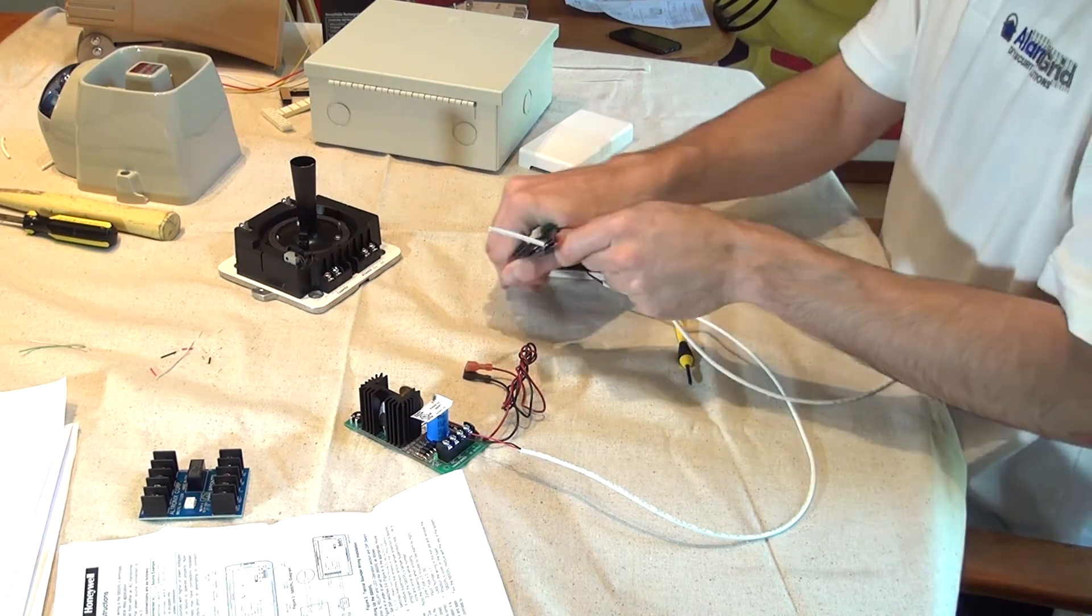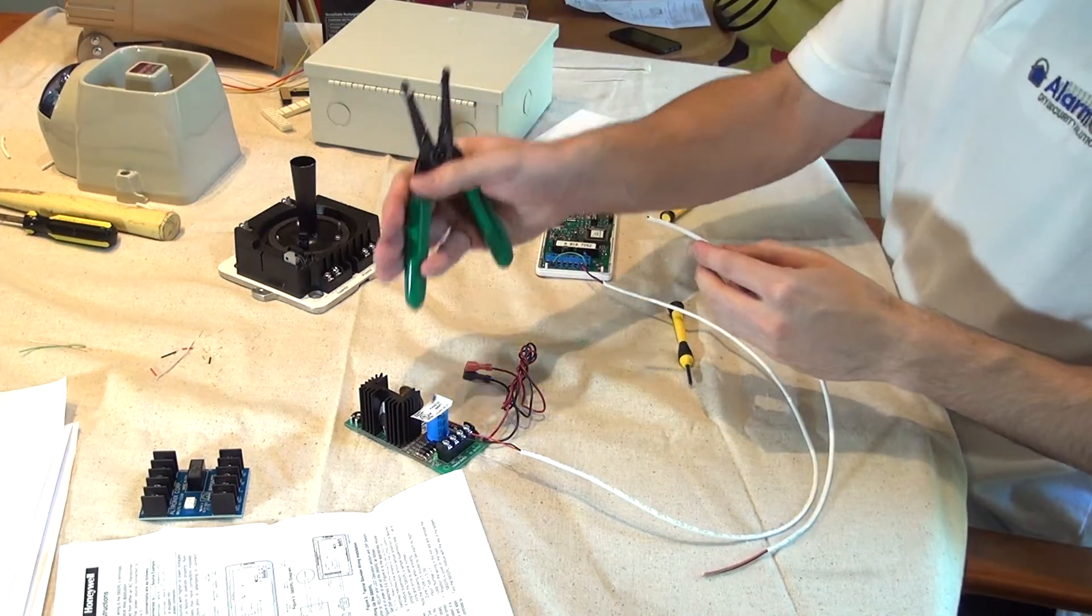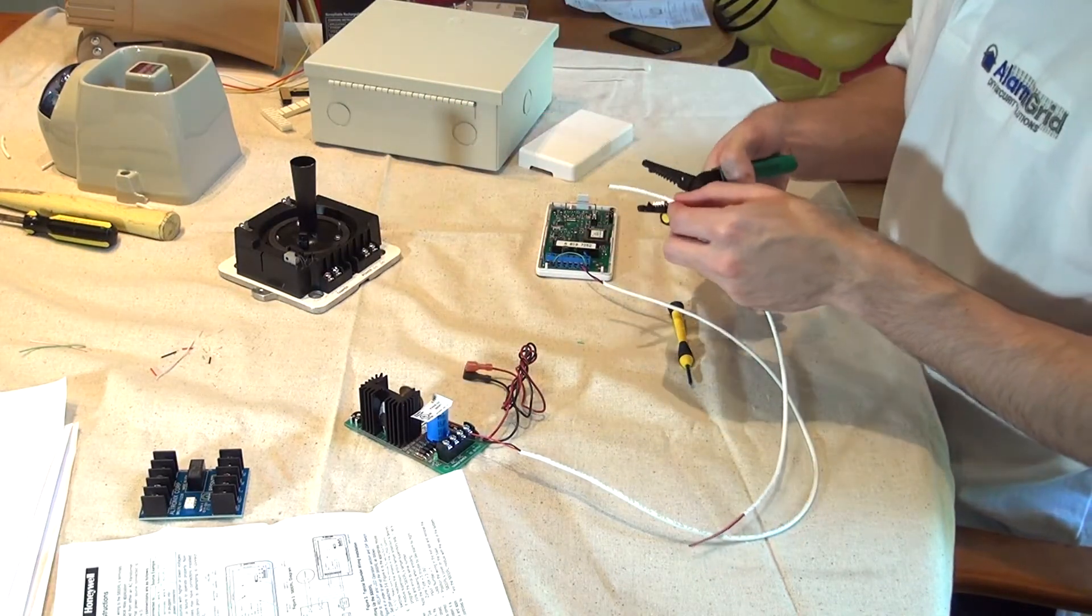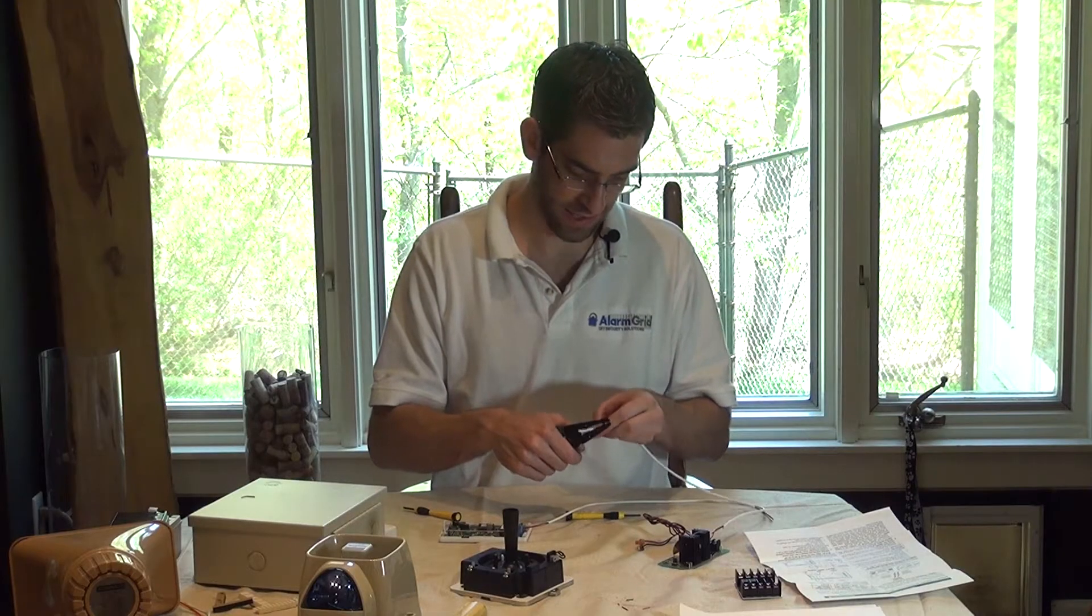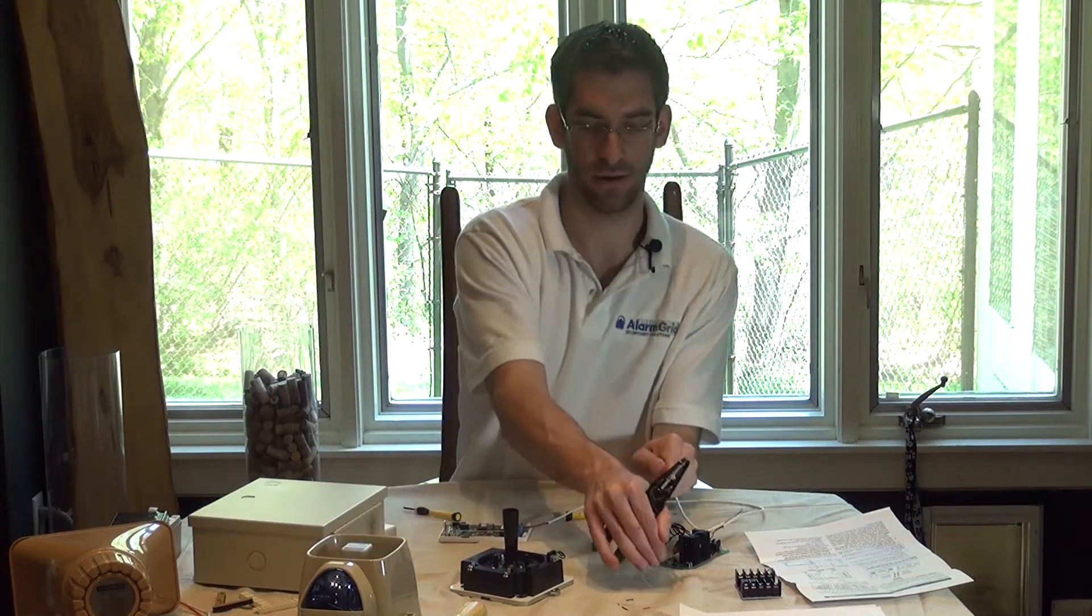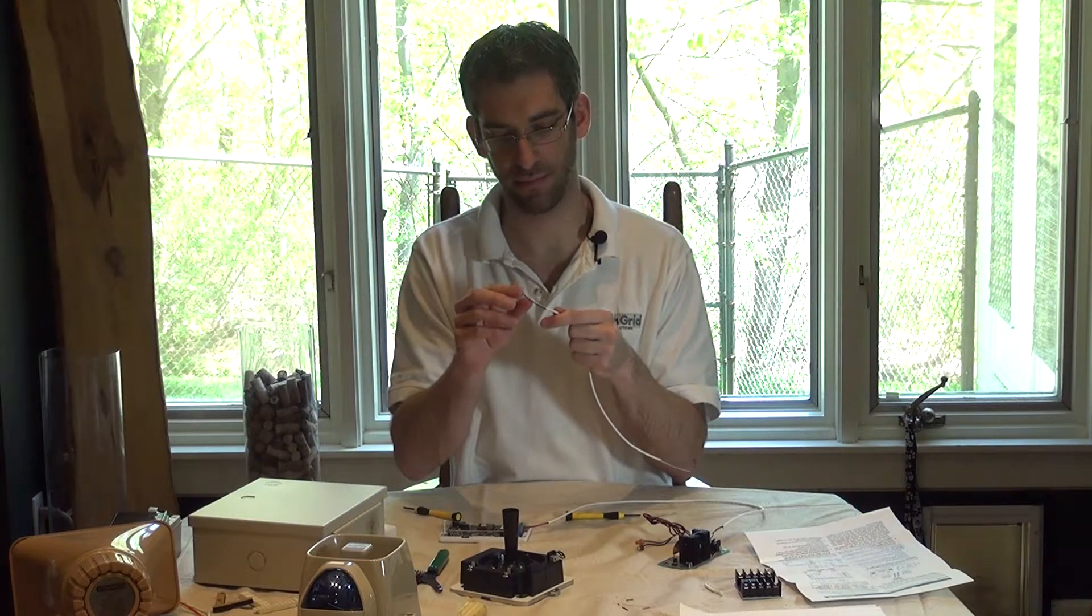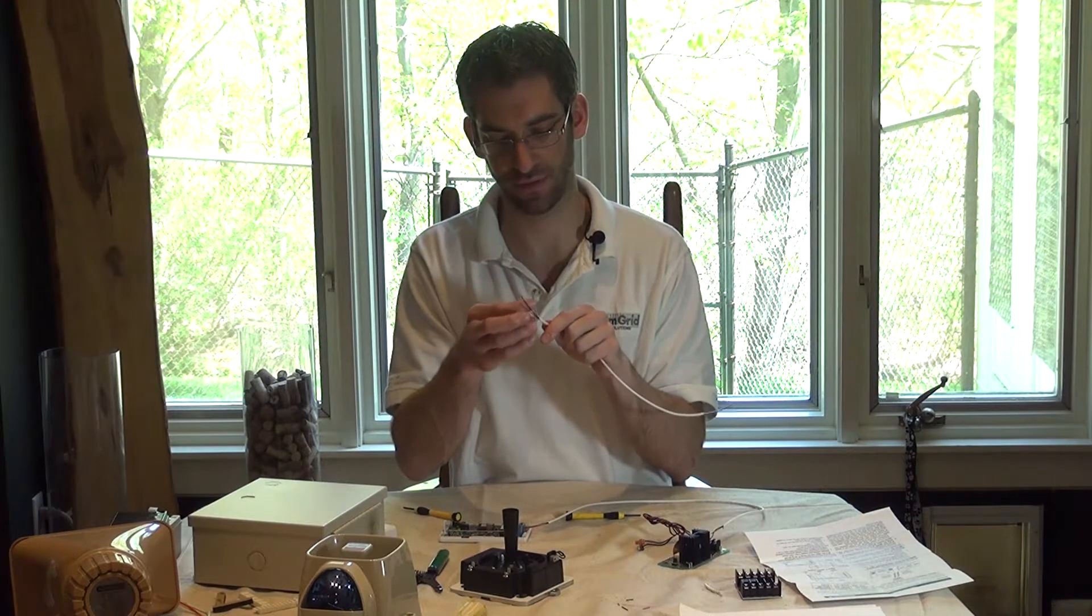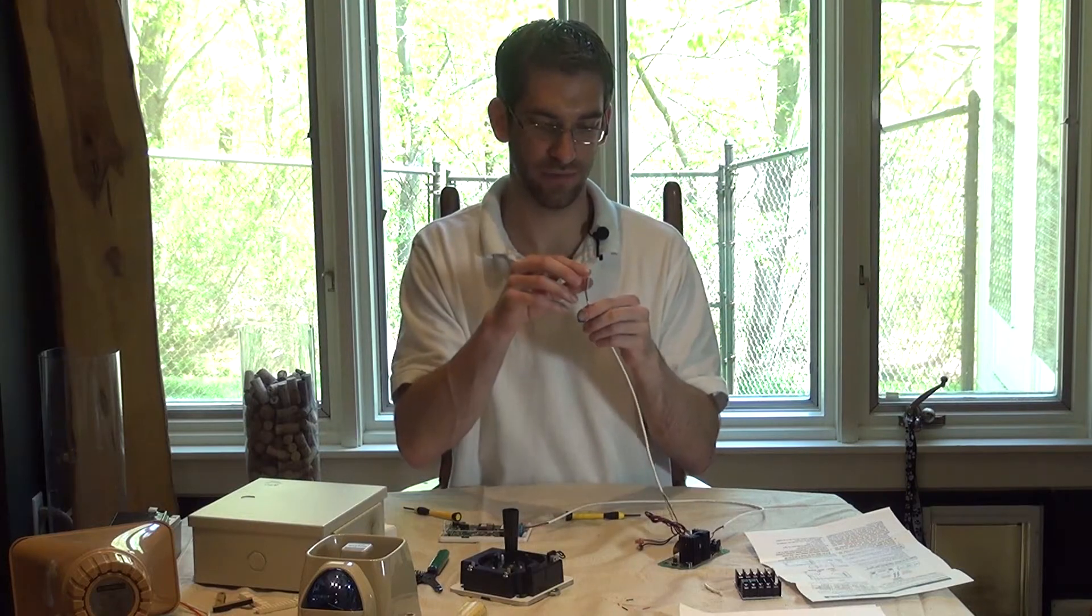You typically need two conductors or two connections from the siren. One going to the power supply and one going to the relay. Because this siren has the built-in strobe, we're going to use the four conductor wire and just double them up. One set of two wires for the strobe and one set of two wires for the siren.